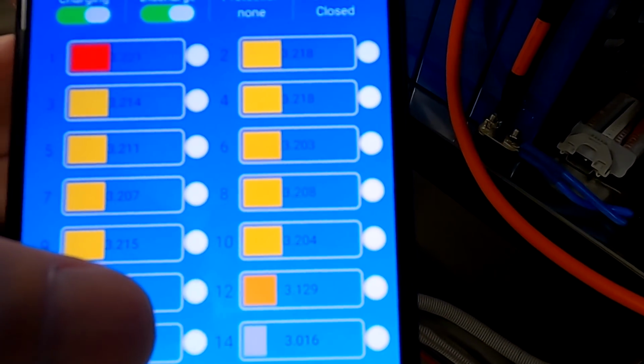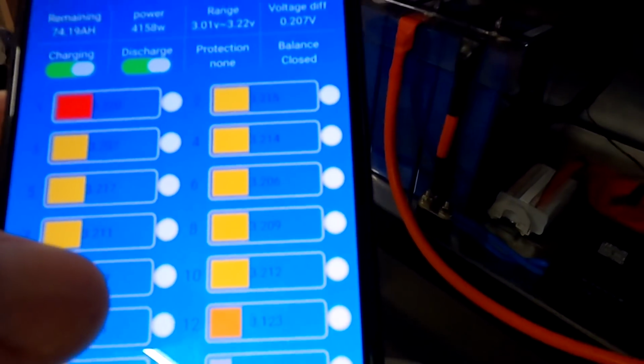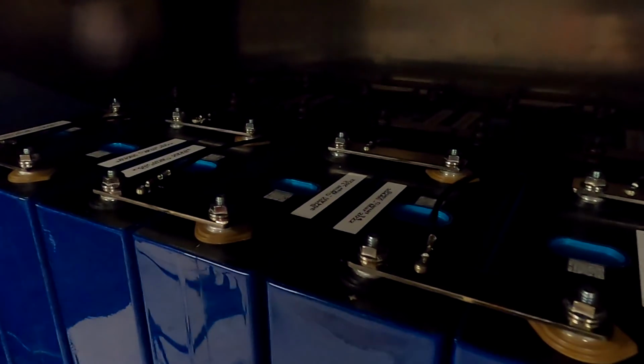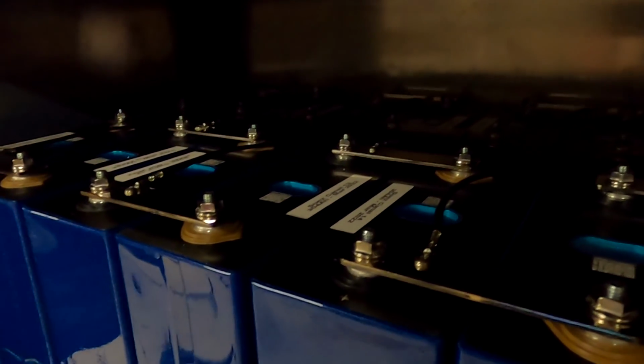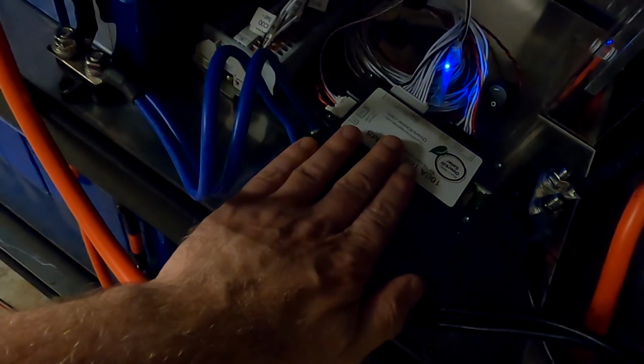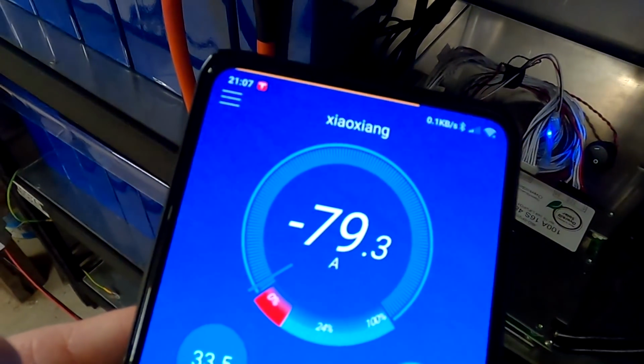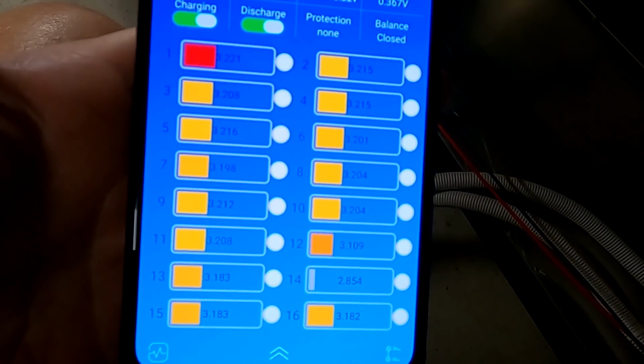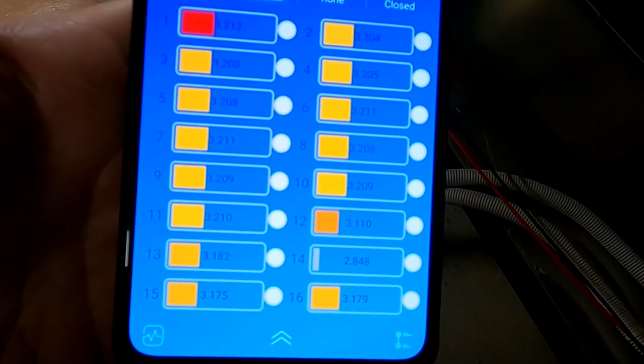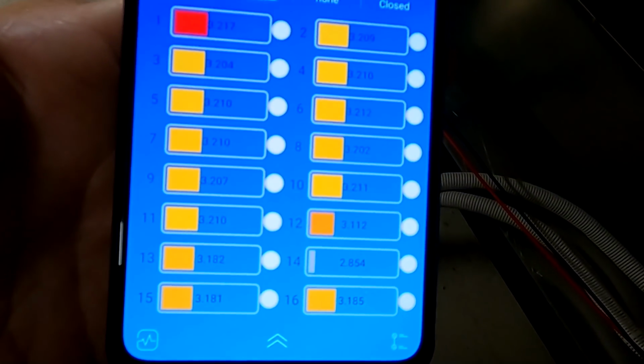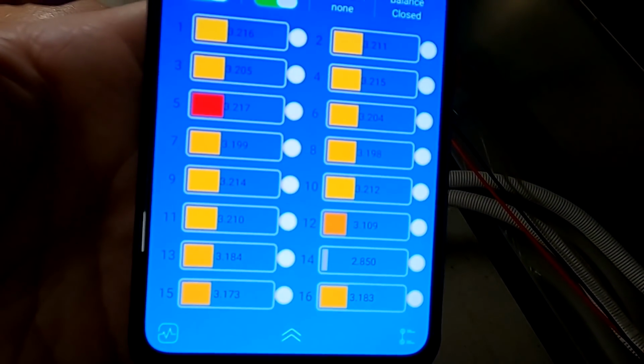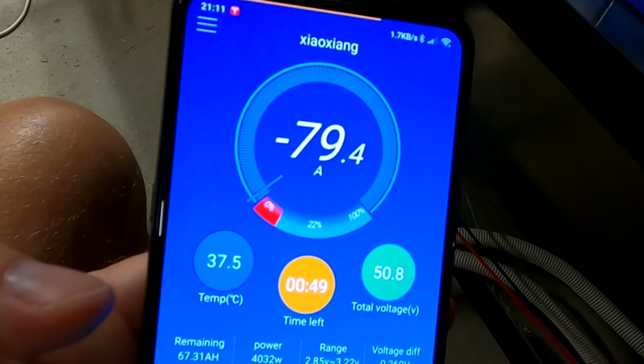And then we do another check with the infrared camera. But so far everything seems to be fine, almost as expected. Nice, oh yeah, the BMS gets warm now, 80 amps. Okay, we are at 2.85 volts now with cell number 14 here, and I think I'll stop the test now. It's been running for 12, 13, close to 15 minutes now on 80 amps.